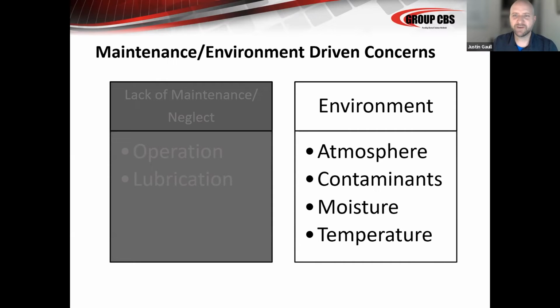While on this point of environment, and you just spoke to this exact question to a degree, I just want to know more. The question is, what kind of environments would reduce lubrication life? You're talking about temperature specifically for lubrication. Are there other things related to that? Yes. So temperature really affects the lubrication. What you have in the environment matters too. If you have gases in the environment that are detrimental to your breaker and the lubricant properties of your lubricants, that will contribute. Any kind of debris or dust that can get into the cabinets onto the breaker is going to cause an issue.